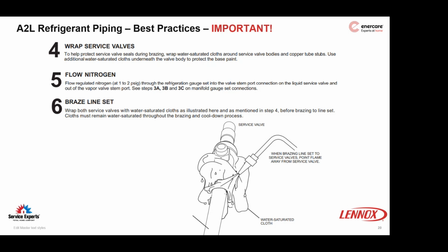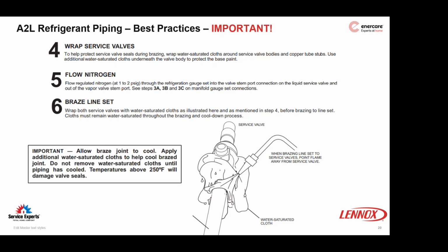I know there's a spray out there, almost like a gel, that will also help keep joints cool. Regardless of your method, let's please make sure we're using an appropriate method to keep the joints or the valves themselves cool. And then, of course, allow them to cool naturally so that we don't crack the joint you've made by hosing it down to cool it rapidly. We don't want to rapidly cool it. We want it to cool naturally so that there's no possibility of undermining the joint's integrity.